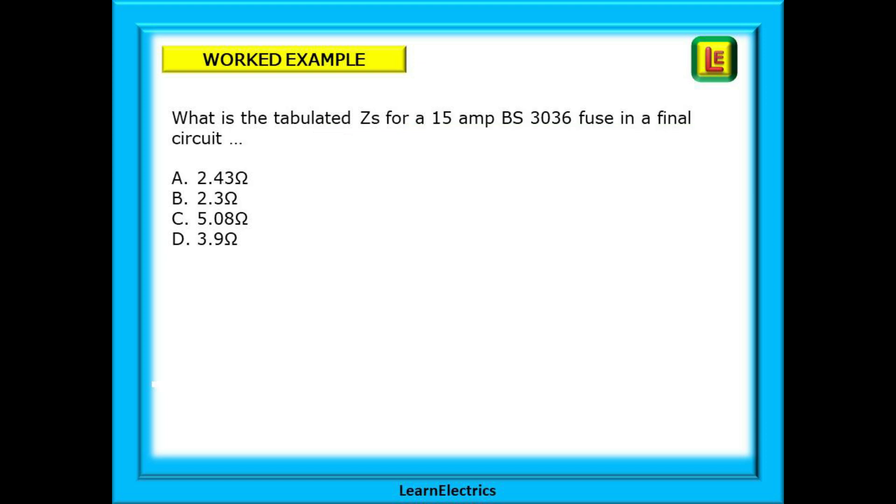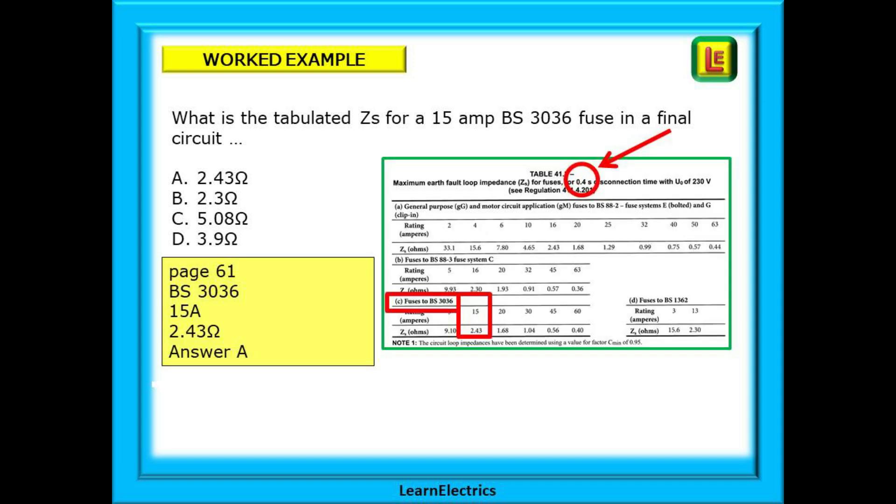Now try this one. What is the tabulated ZS for a 15 amp BS 3036 fuse in a final circuit? Fuses again but a final circuit this time and that means 0.4 seconds. We need page 61 table 41.2. Find BS 3036 fuses. Find 15 amps and there is our answer 2.43 ohms. Choose answer A.